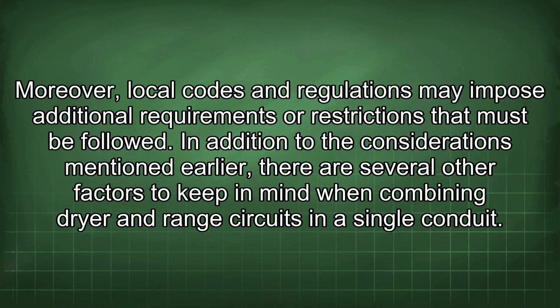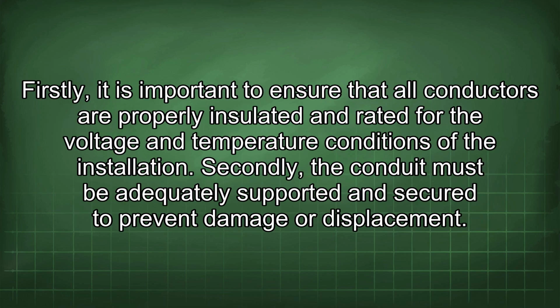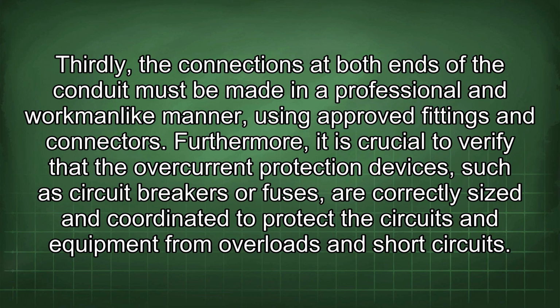In addition to the considerations mentioned earlier, there are several other factors to keep in mind when combining dryer and range circuits in a single conduit. Firstly, it is important to ensure that all conductors are properly insulated and rated for the voltage and temperature conditions of the installation. Secondly, the conduit must be adequately supported and secured to prevent damage or displacement. Thirdly, the connections at both ends of the conduit must be made in a professional and workmanlike manner, using approved fittings and connectors.